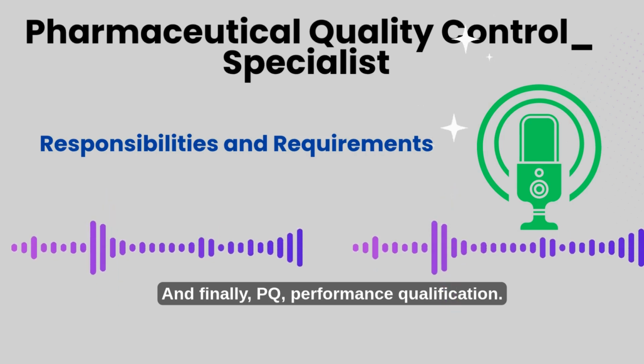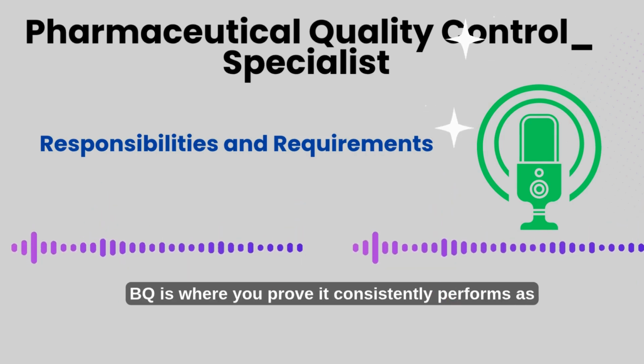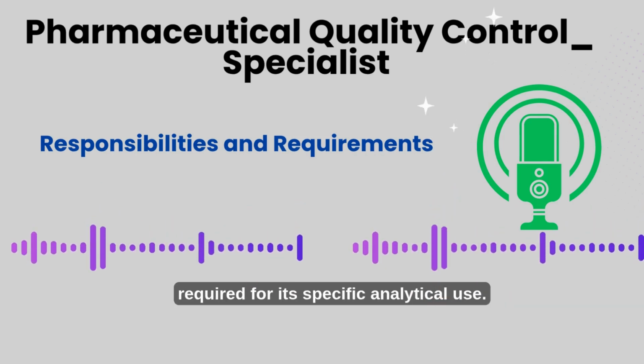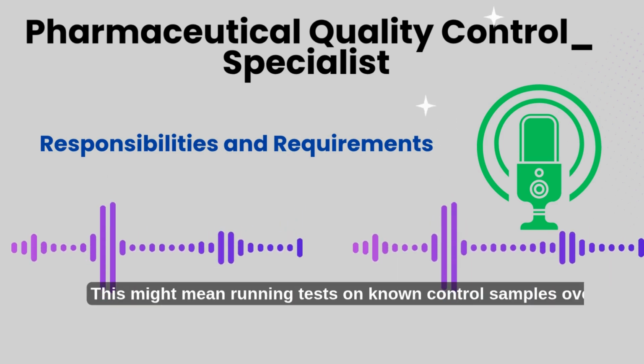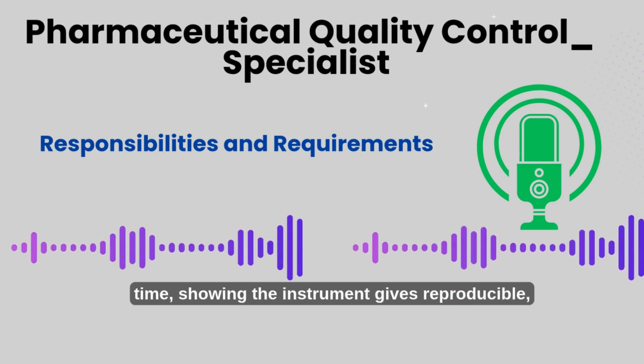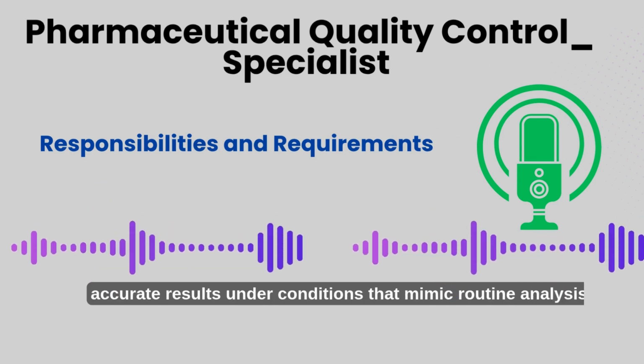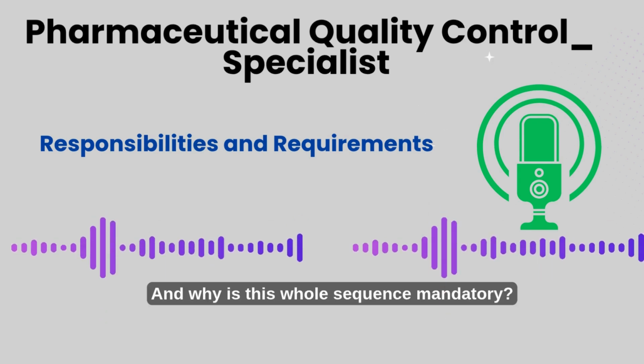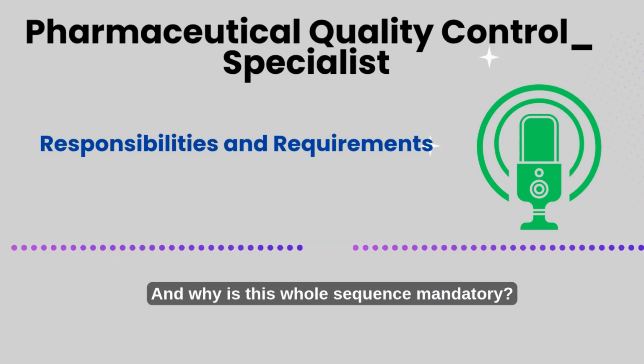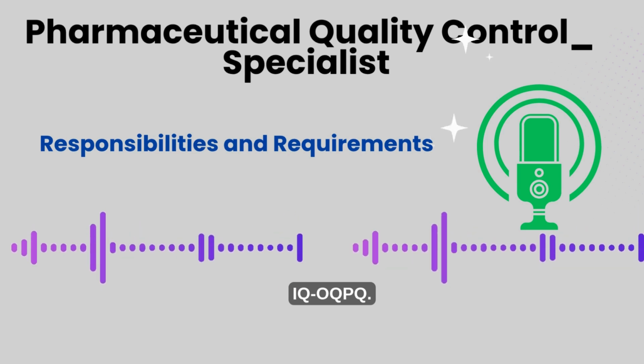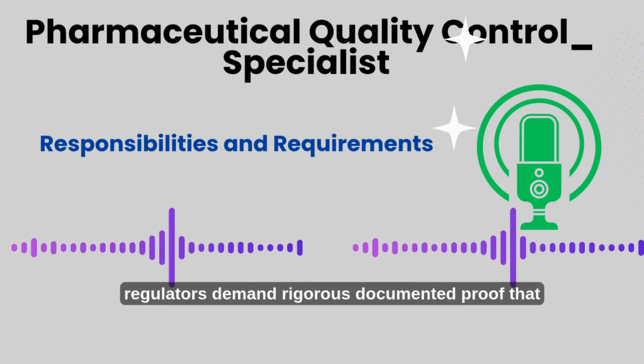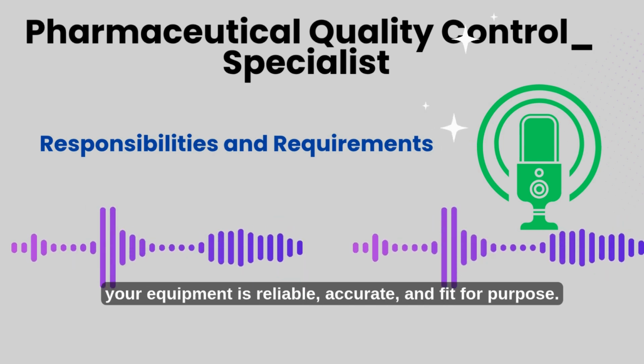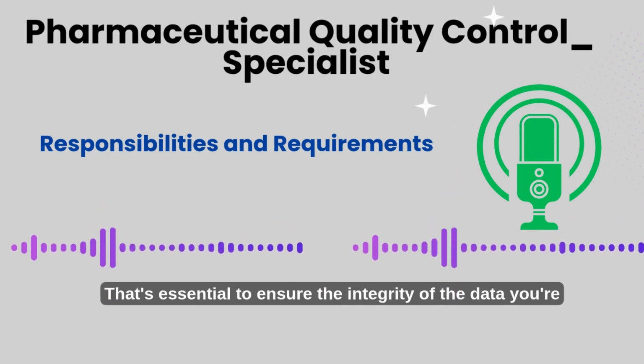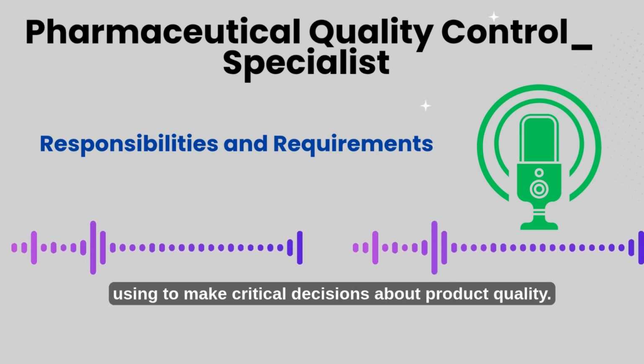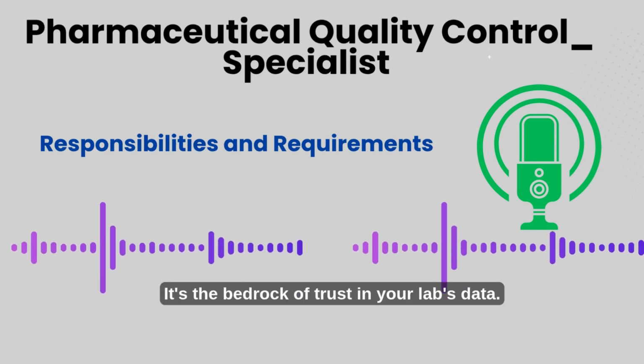And finally, PQ, performance qualification. PQ is where you prove it consistently performs as required for its specific analytical use. This might mean running tests on known control samples over time, showing the instrument gives reproducible, accurate results under conditions that mimic routine analysis. And why is this whole sequence mandatory? IQ, OQ, PQ. Because regulators demand rigorous, documented proof that your equipment is reliable, accurate, and fit for purpose. That's essential to ensure the integrity of the data you're using to make critical decisions about product quality. It's the bedrock of trust in your lab's data.